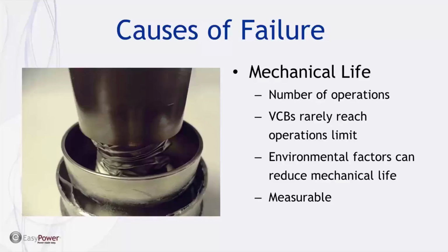Another cause of failure is the mechanical life. Those spring bellows that we talked about before are rated for a certain number of operations. This is highly reliable, but occasionally, depending on the application, sometimes they can exceed these number of operations. Circuit breakers generally don't reach the full number of mechanical operations, but contactors, on the other hand, which are operated many times a day, usually can reach this mechanical life.